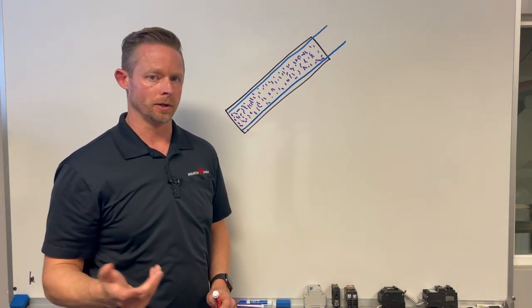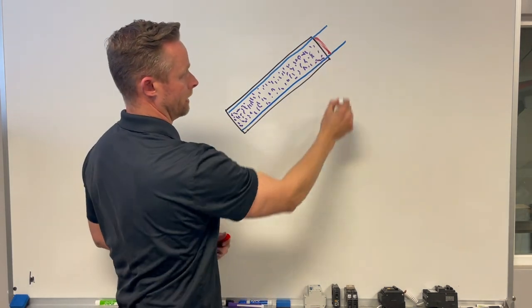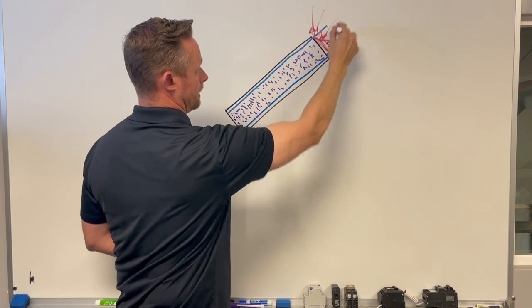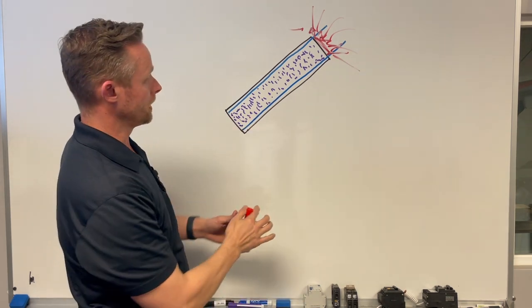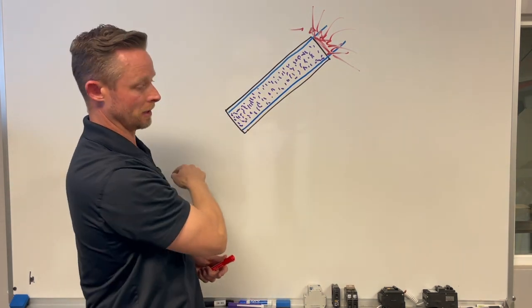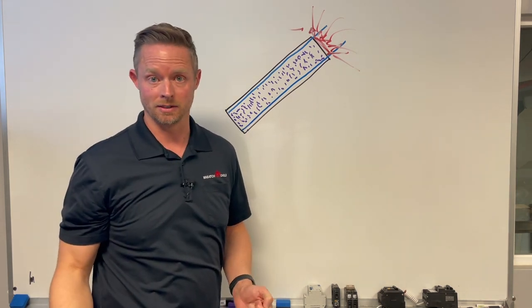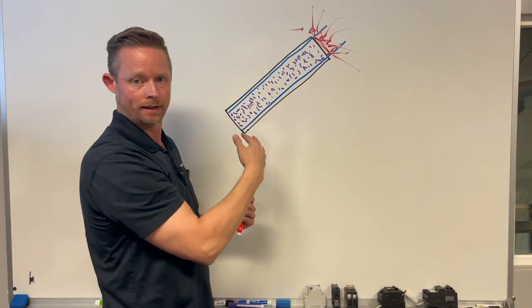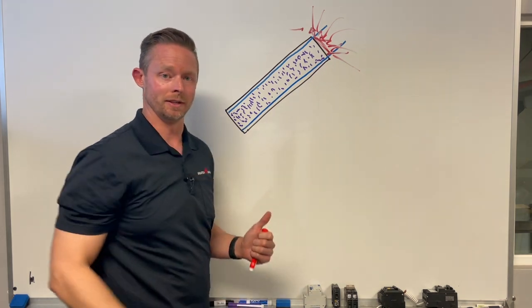So why is this so critical? If you had a spark right here and let's say it started going crazy and started arcing and creating a mess of fire out here, you've still got a continuous feed coming back to a breaker. So the breaker doesn't actually have any signal saying something's wrong. Your heat cable is sending everything back and it's not receiving any information saying that you have an issue on the end of the heat cable.